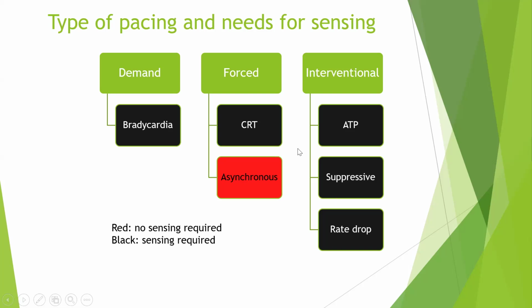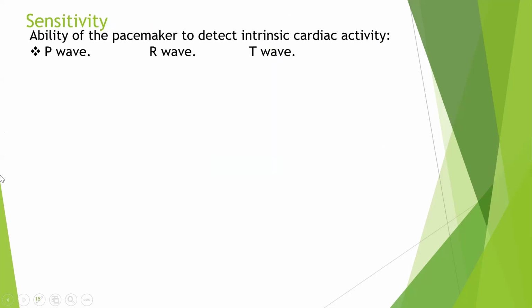If you have a patient who keeps developing VT, what do you do? You try to pace the ventricle at a higher rate to suppress any new ventricular episode. Or it can be used even in the atria. If the patient has recurrent episodes of paroxysmal atrial fibrillation, then you want to pace the atria at a higher rate to suppress any atrial arrhythmia. Rate drop is a type of pacing that you don't really need to know, it is almost dying, but it requires intrinsic sensing. So if you look at all types of pacing, the only one that doesn't need sensing is asynchronous pacing.